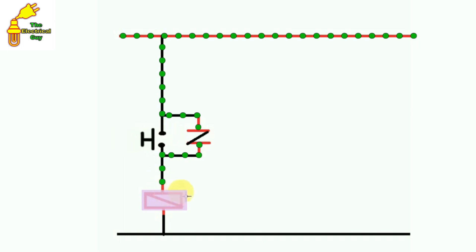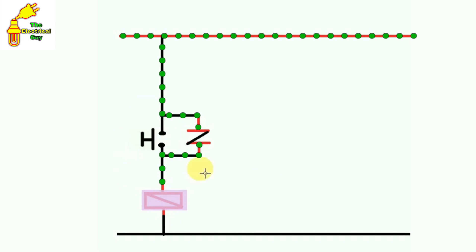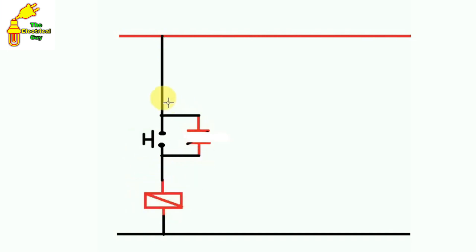So when the contactor turns on it becomes NC. Now even if we release this push button, still this contactor remains on because this auxiliary contact has become NC and current is flowing through this auxiliary contact to the coil of the contactor. The contactor will remain on always. Now if we want to turn off this contactor, how can we do this?